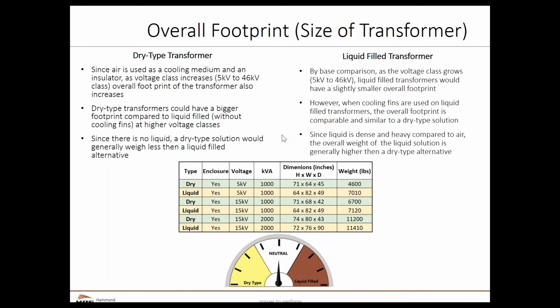Overall footprint is an interesting topic, and we've seen some liquid fill manufacturers say that their footprint is a lot smaller than dry type. The issue with some of those claims is you've got to be careful. When they're talking about footprint, oftentimes they may be talking about the part of the transformer that physically is attached to the concrete, let's say. But they may not be taking into account the fact that I've got 3 feet of cooling fins hanging off the back of the transformer. And while those don't mount directly to the ground, and technically there's no footprint below that, I have to have something to mount it to, they still take up room.